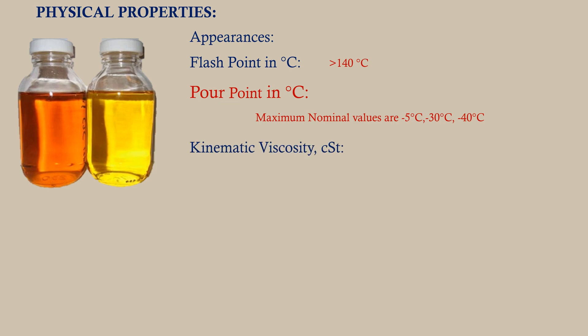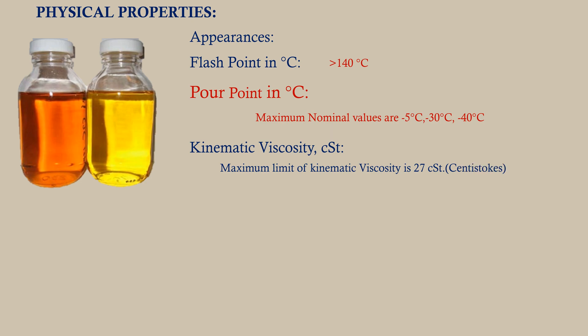Maximum nominal pour point values are minus 5°C, minus 30°C, and minus 40°C. Kinematic viscosity in CST: the kinematic viscosity of transformer oil is the resistance to continuous flow of oil without the effect of external forces. Low viscosity means low resistance to flow. Viscosity affects the cooling performance of the transformer, so good transformer oil should have low viscosity. The maximum limit of kinematic viscosity is 27 CST.